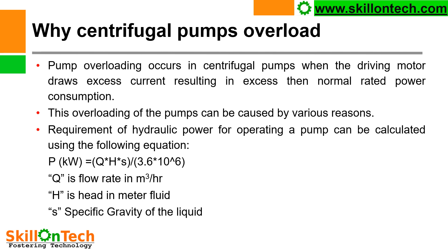The requirement of hydraulic power for operating a pump can be calculated using the following equation: Power (kW) = Q × H × S / (3.6 × 10^6), where Q is the flow rate in m³/hour, H is head in meters of fluid, and S is the specific gravity of the liquid handled by the pump.